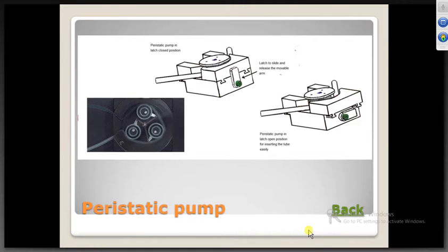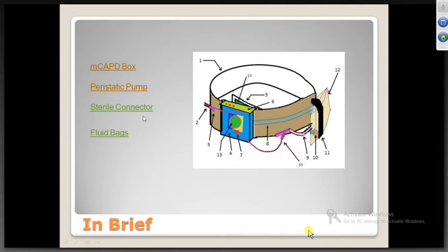This is available the world over. A lot of people are doing it. But what we have achieved is micro-miniaturization. In our peristaltic pump you can just open up this latch, it will slide out, and you can just connect this tube, because in our case the patient has to put in one tube every day, so that at night when the dialysis is over and he goes back home, he has to discard this particular sterile connector. So we need a mechanism wherein the patient can insert it automatically and easily. This is something we have thought about over many months, with many inputs from many students and working professionals, and they have got it to this level.